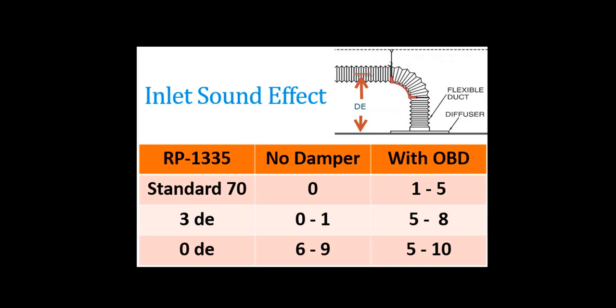When you add the opposed blade damper, the jump in sound happens at the 3 equivalent duct diameter installation. Also noteworthy is that with zero equivalent duct diameter or a 90 degree elbow leading straight into the diffuser, the sound add for with and without a damper is essentially the same.